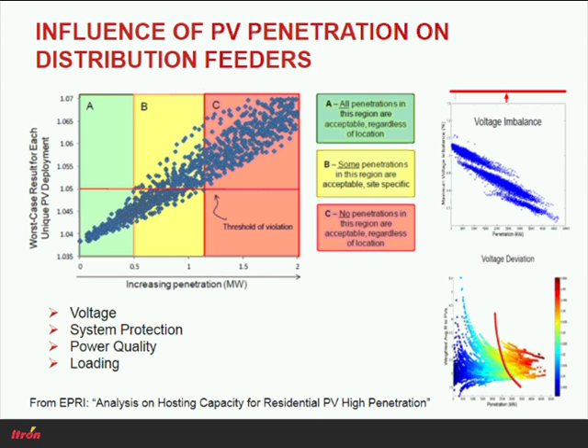and you can run into thermal overloads. One of the other key takeaways from some of the work that NREL and EPRI and some of the other utilities have found is that even though all of these factors can be occurring in distribution systems anyway, PV tends to exacerbate the problems. And where PV is located on a distribution feeder is important. The further out from a substation on a radial system, PV tends to cause bigger problems, as well as larger PV systems tending to have bigger problems than smaller PV systems. But again, there's a host of factors that go into this. EPRI has done some very interesting work on what they call hosting capacity, to begin looking at how much PV you could actually add into the grid and not run into some of these reliability issues.